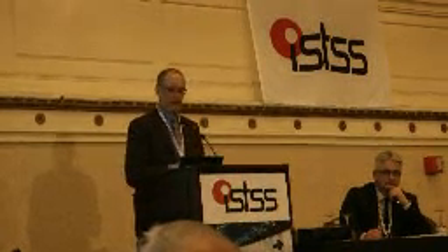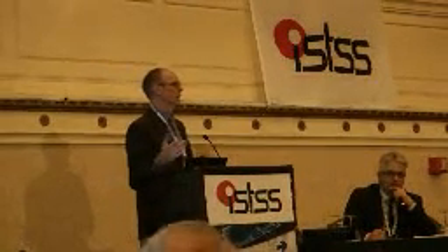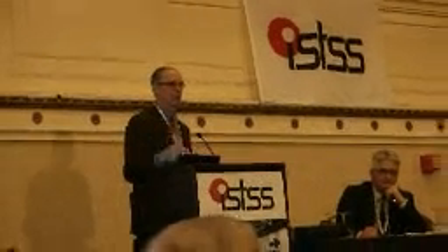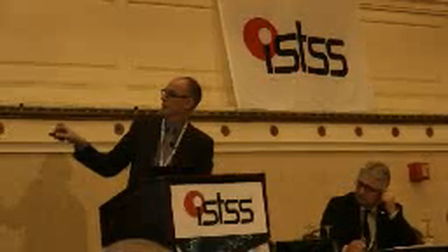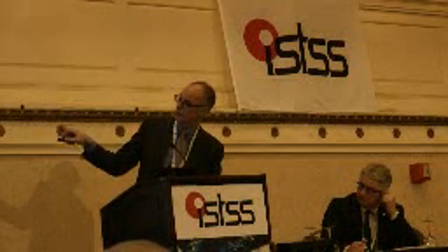It's good to know that the sprinkler is designed to protect the tunnel lining and the tunnel's construction. About 40% of the sprinkler water is reflected back to the tunnel lining to cool down the tunnel structure as such. At the same time, a ventilation system is started, and a fourth sprinkler section. The ventilation system is used to force the smoke and the hot gases in a certain direction and through the two sprinkler sections behind the fire position.